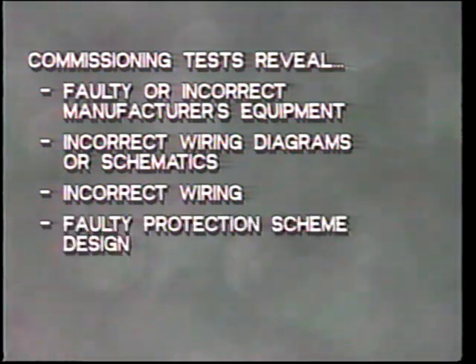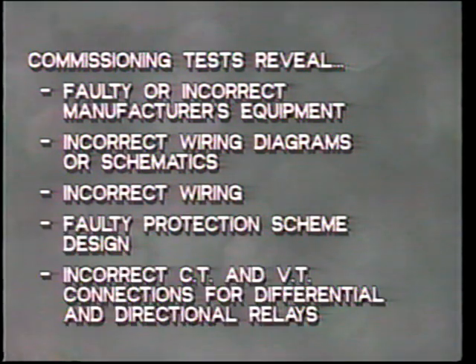We have been looking at a broad overview of commissioning tests. Make sure that you become familiar with your own company's procedures. Conscientiously performed, commissioning tests should bring to light problems such as faulty or incorrect manufacturer's equipment, incorrect wiring diagrams or schematics, incorrect wiring, faulty protection scheme design, incorrect CT and VT connections for differential and directional relays. Detecting these problems right at the beginning will certainly reduce the need for troubleshooting later. More importantly, it will provide the relay protection required to ensure system integrity.